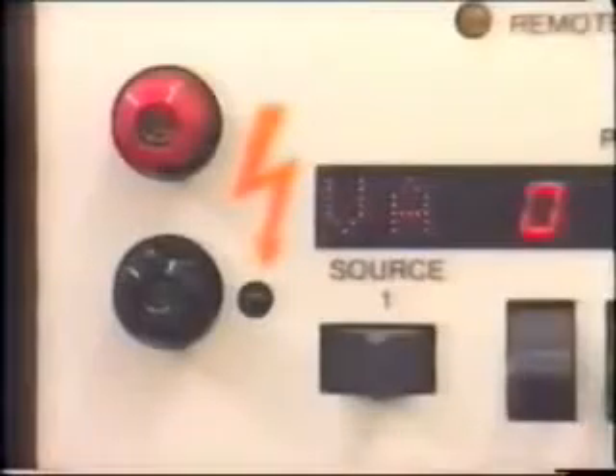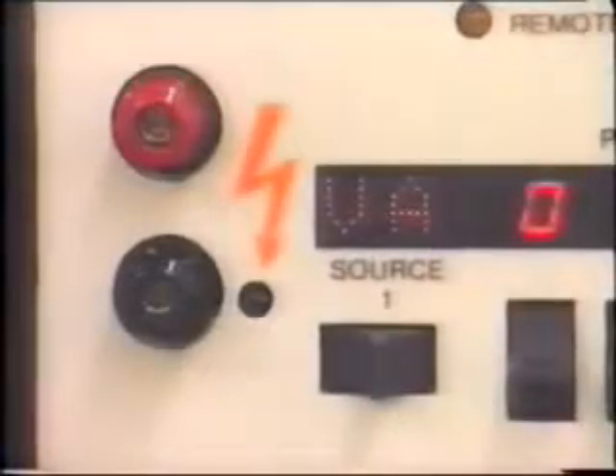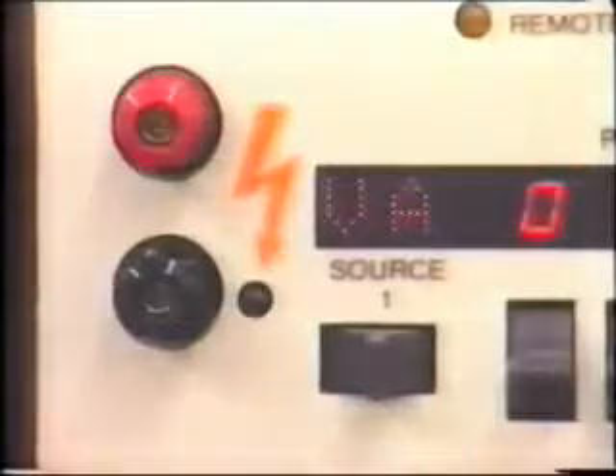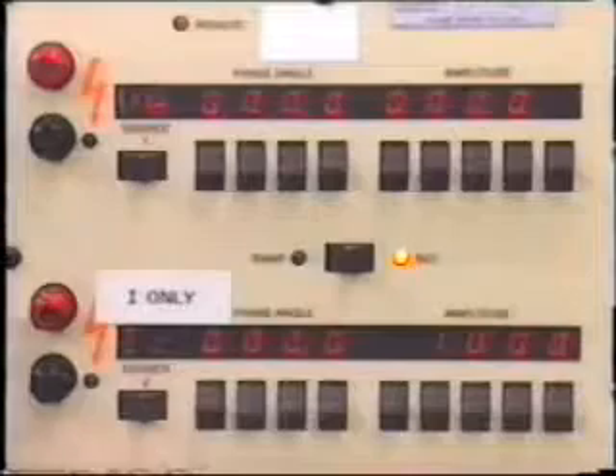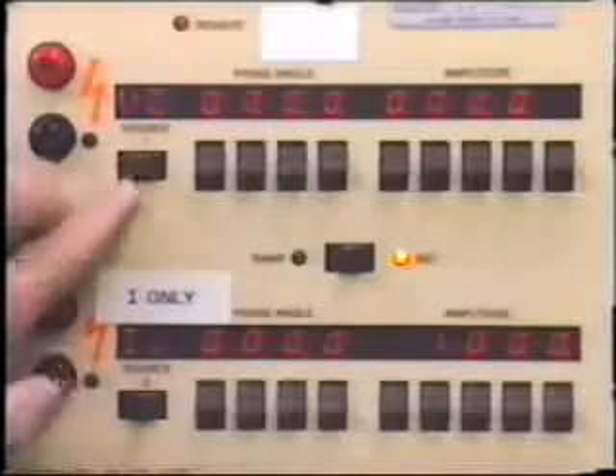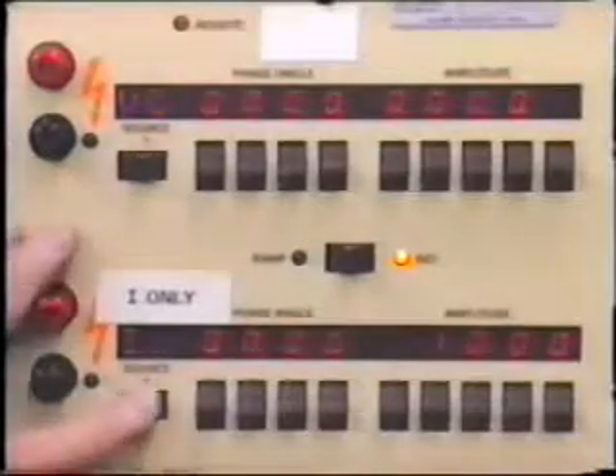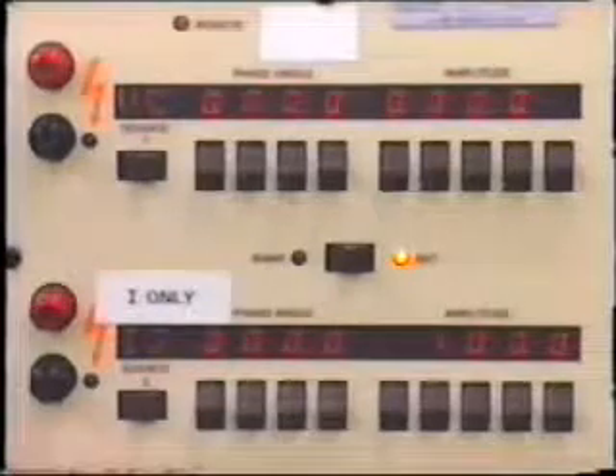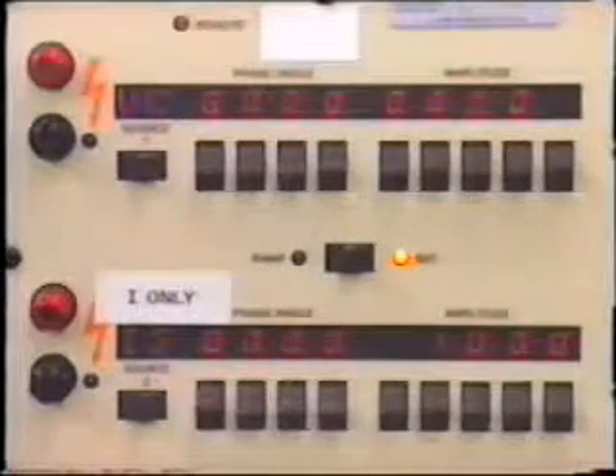The black output terminals are grounded for protection. These light-emitting diodes, or LEDs, flash to indicate when the outputs exceed 20 volts AC. The default source designations, VA and I1, can be changed by means of flipper switches to keep track of phases when we are doing multi-source testing.